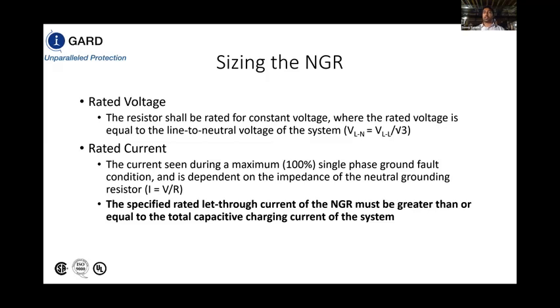When it comes to rated current, usually for low voltage systems, 5 amps or 10 amps is selected for 480 volt and 600 volt systems. And for systems that are approaching 4160, 13.8 kV, and 25 kV, we need to entertain a concept called charging current, and we need to calculate how much charging current is to be expected from the system in the pre-design stage. Now, charging current is based on the idea that there is a capacitance that exists between conductors and ground. This capacitance basically is dictated by the amount of cabling that you have leading out to the loads, as well as the loads themselves and the source itself. The loads and the source do not contribute as much. It's more so the cabling.